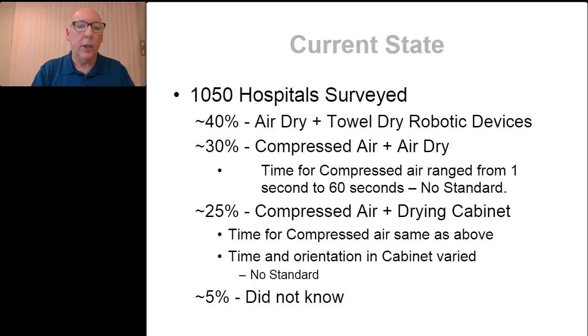So recently, there were over 1,000 hospitals surveyed relative to drying robotic devices, and here's what came out of the survey. About 40% air dry or towel dry robotic devices. About 30% use compressed air plus drying with air, just the air drying. And the time for compressed air varied, ranging from 1 second to 60 seconds. There was really no standard.